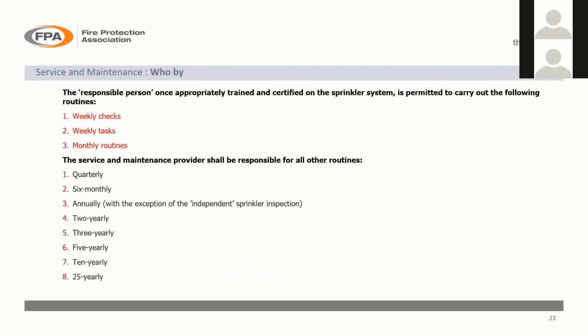So moving on, the responsible person, once he or she has been appropriately trained and certified on the sprinkler system, is permitted to carry out the weekly tasks and the monthly tasks. I will be running through these pretty quickly, but then you need to go to a service and maintenance provider, and they'll be responsible for all the other routines. Now, you probably have a contract with the maintenance provider. It's worth pointing out at this point that you should, as the user, look at this contract, and every time you come to renew, make sure that it is current to what you've actually got there. So if you've got more than one building, or you've enhanced your system in some way or other, run through it and make sure that any changes that have occurred are written into the contract with the maintenance contractor.